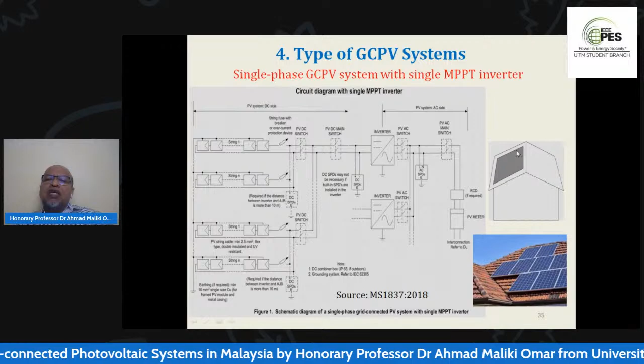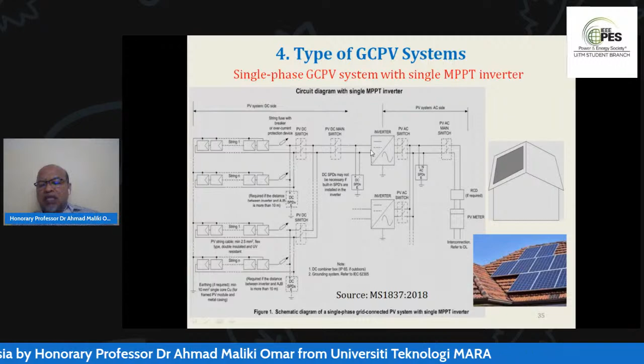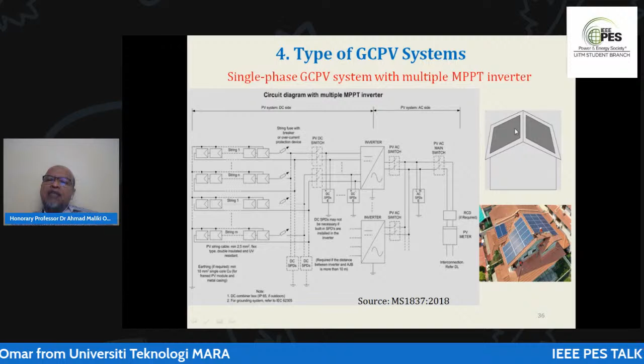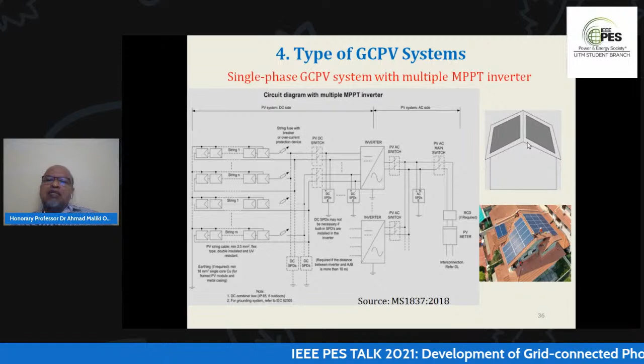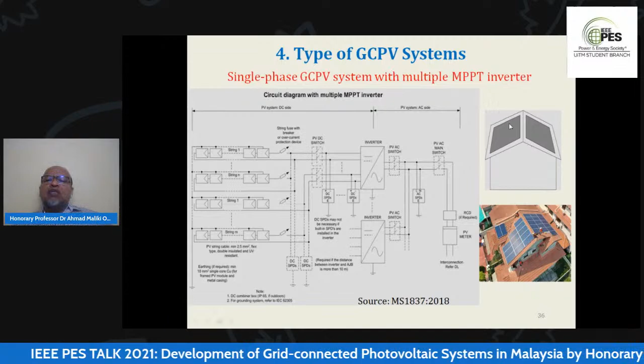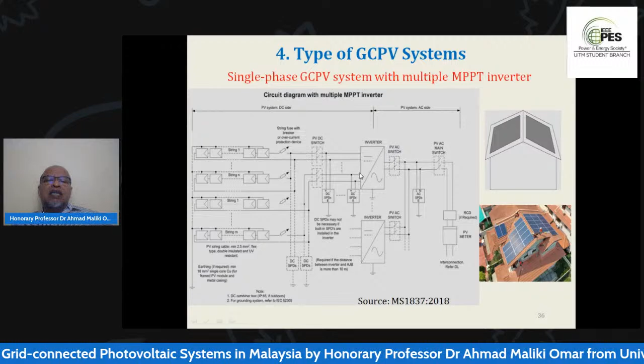You might wonder what single MPPT means. Normally if you have only one side of your house to install on, it's okay to have one MPPT inverter. But if you have multiple orientations - one side facing north, another facing south, for example - it's advisable to use multiple MPPT. So you need a multiple MPPT inverter, with one MPPT connected to one side and another MPPT connected to the other side, so the system is optimum.